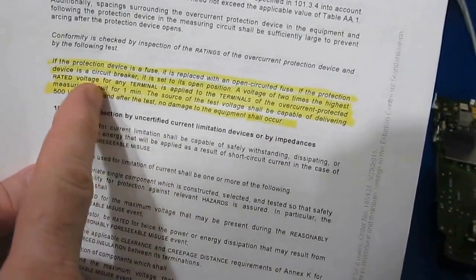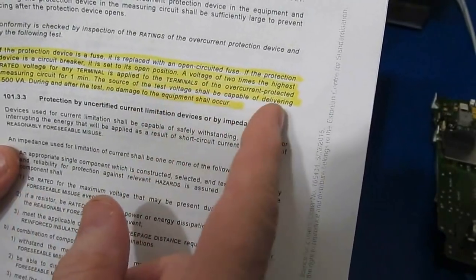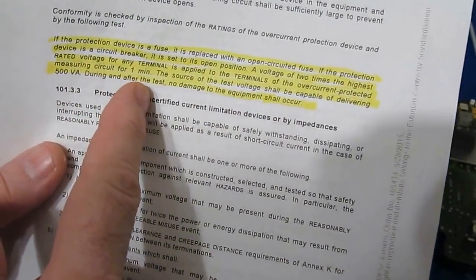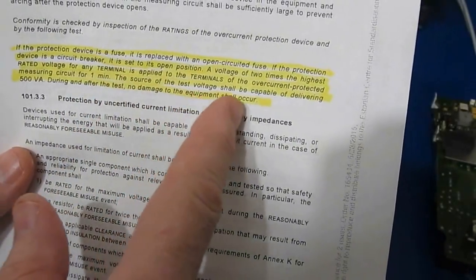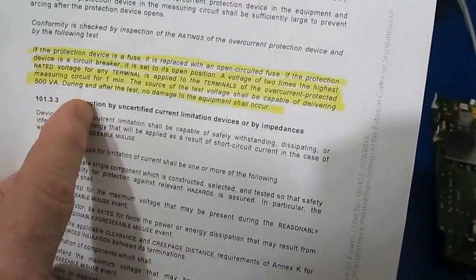The voltage of two times the highest rated voltage for any terminal is applied to the terminals of the overcurrent protected measuring circuit for one minute. The source of the test voltage should be capable of delivering 500 VA.